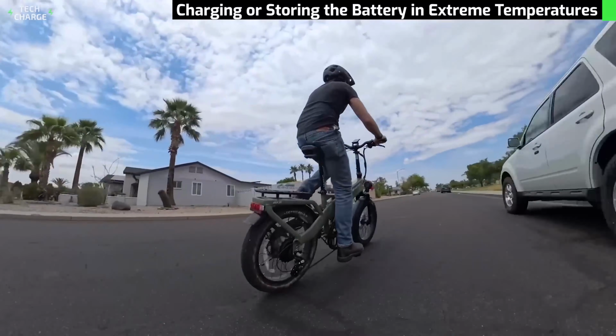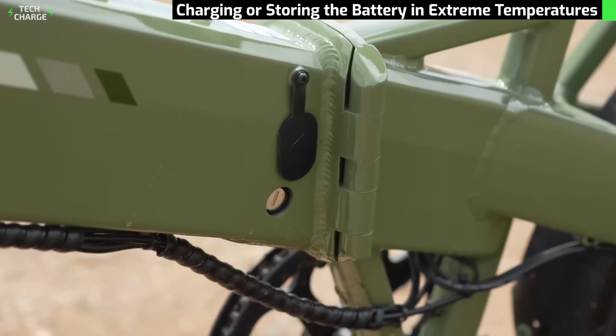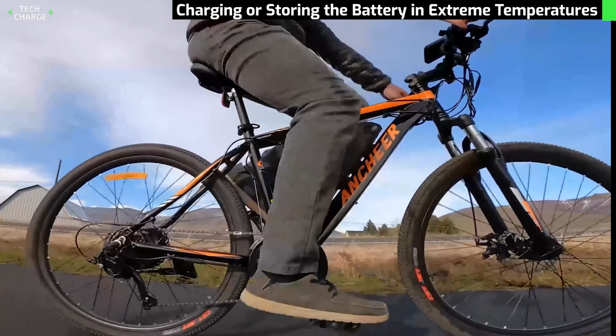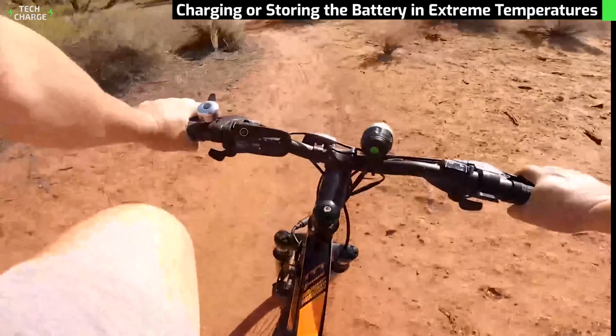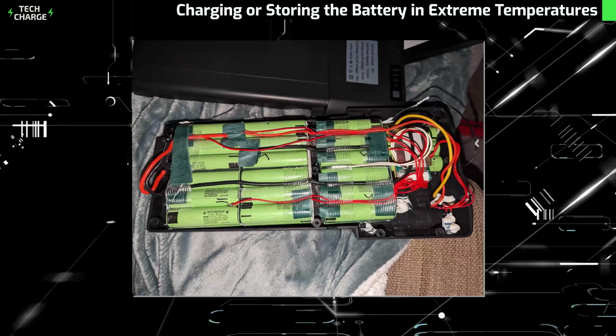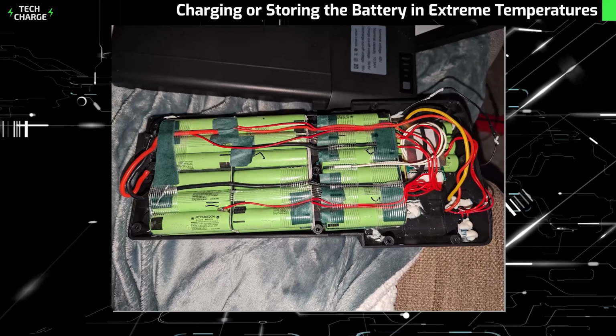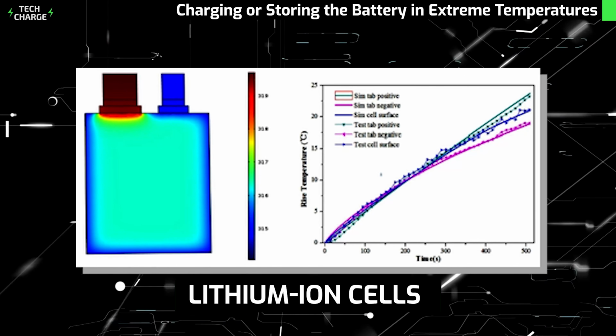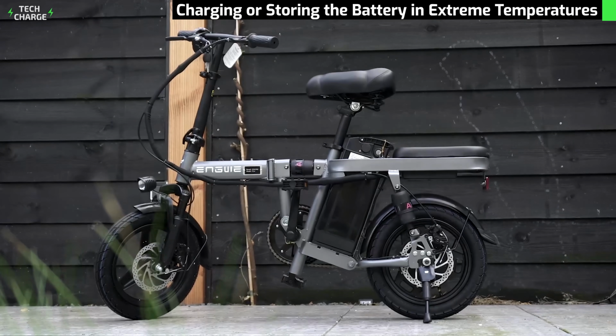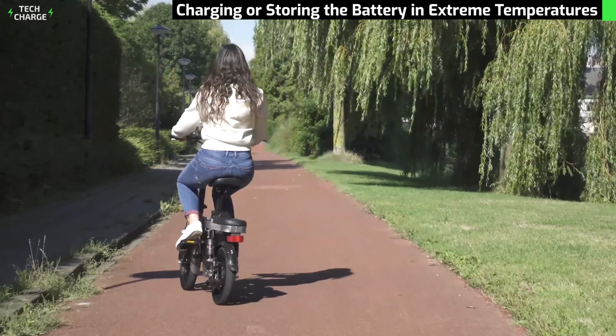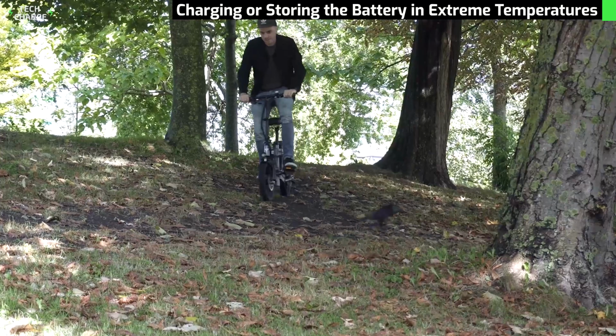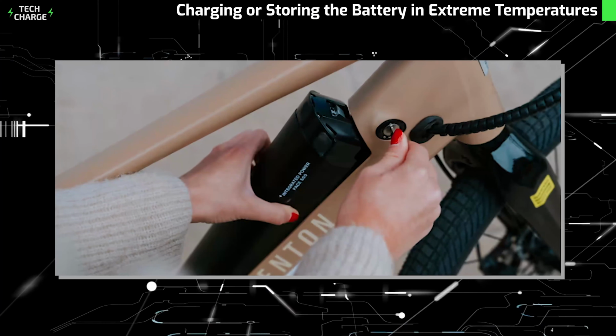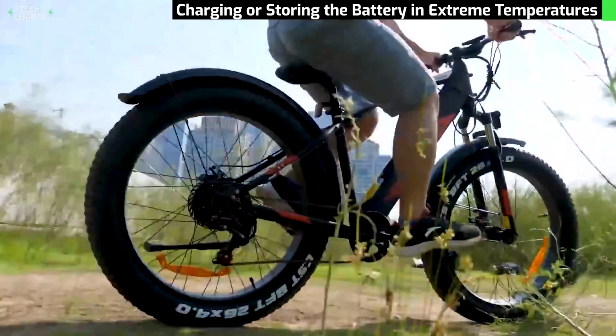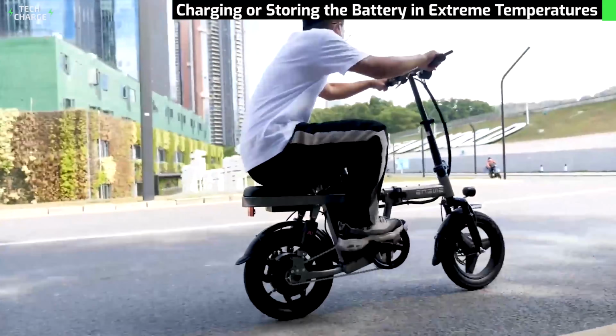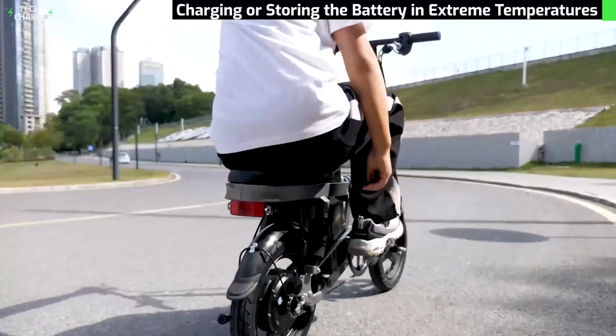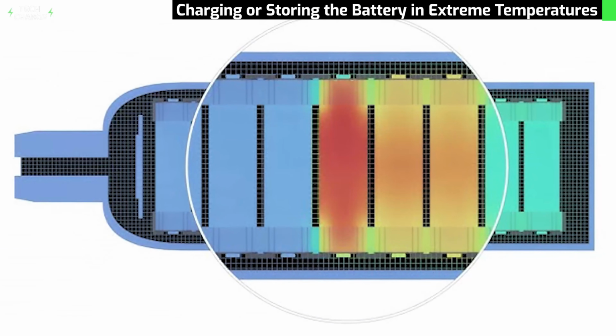High temperature creates the opposite problem. Excessive heat during charging or storage stresses the internal chemistry and, more critically, reduces the battery's ability to dissipate the heat naturally generated during the charge process. Lithium-ion cells always produce some heat during charging as electrical energy converts to chemical potential. Normally, this heat dissipates into the surrounding environment. But when ambient temperature is already elevated, that heat has nowhere to go. Internal temperature rises faster, shortening the time to reach the critical threshold where thermal runaway initiates.